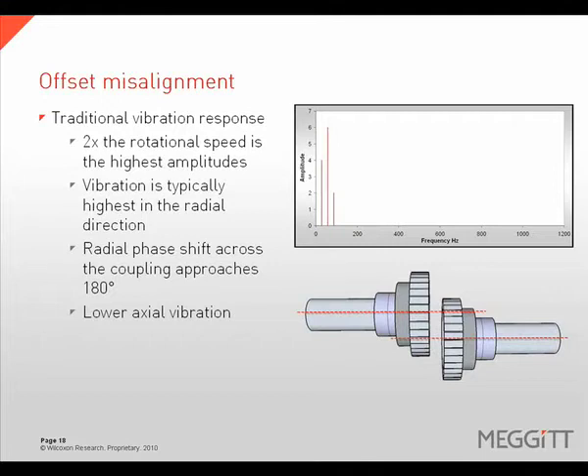This assumption can often be misleading, as a combination of the two types will create a vibration that is not purely directional in one measurement plane or the other. Offset misalignment is traditionally characterized with a 180-degree phase shift across the coupling in the radial direction. It is important to look at the machine as a whole, and pure offset misalignment will typically exhibit lower axial readings compared to the radial readings.